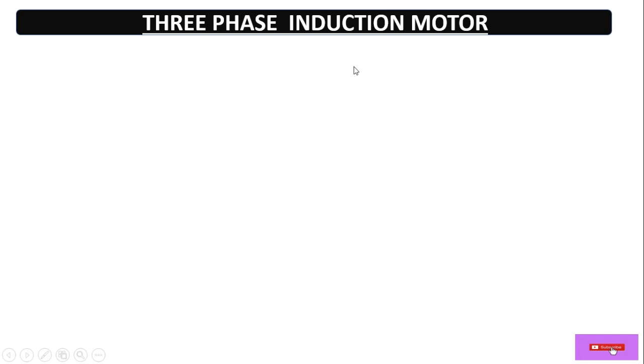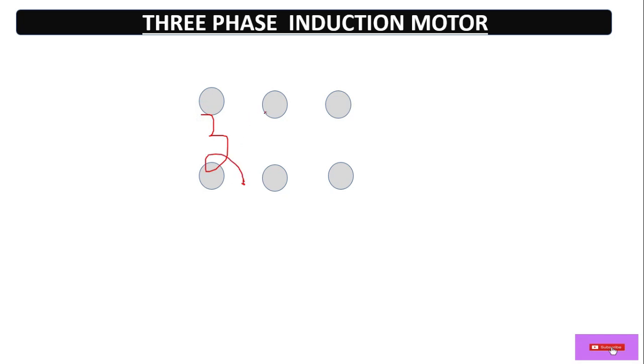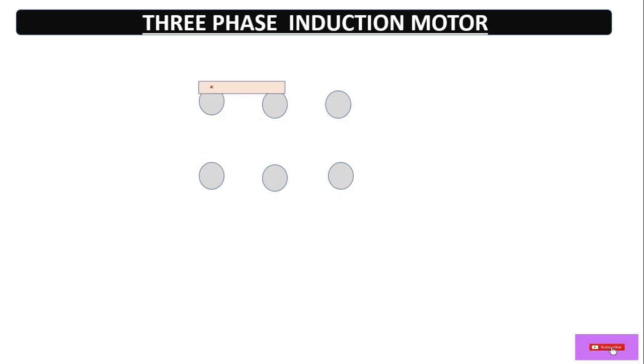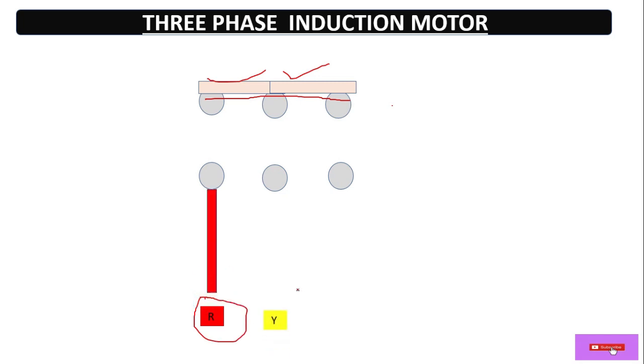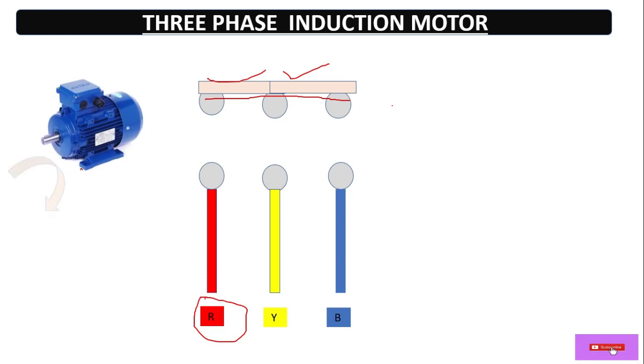This is about the three-phase induction motor — basically how to change the direction of a three-phase induction motor. This is the terminal block, the terminal box of the three-phase induction motor. Generally there are six terminals for each winding. So here the windings are internally connected. We have a three-phase winding, so let's make a star connection — short all these windings at one terminal and connect them together with the help of this strip. Now let's give the power supply — three-phase power supply — so here this is the R phase, and we have provided R, then Y, then B. In this condition our motor rotates in the forward direction, means clockwise direction.